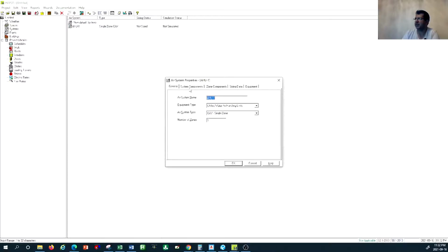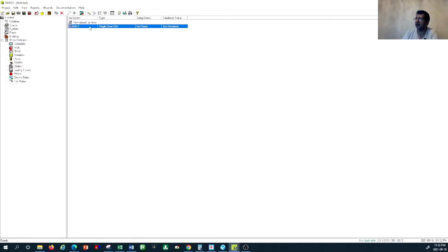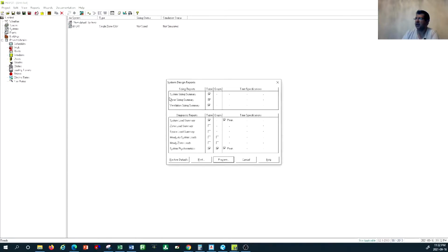And when I completed the scheduling and everything on a high level, on the system component, if you come to the central cooling side, our supply air is going to be 56 degree Fahrenheit. And as you can see, the coil bypass factor, this is the same coil bypass factor I just mentioned. So I assume this to be 0.1 of the coil bypass factor. And then based on that, and the maximum supply air temperature of 75 degree Fahrenheit in the cooling mode, I calculated everything, and then I want to review the design parameters here.